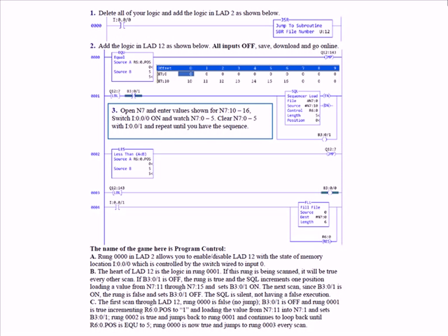In other words, this will not continue to create loopbacks once it's gone through 5 increments until you execute rung 4. When you turn on input 1, that clears R60, and it also clears N70, and you can start over again. So this is just a little demonstration of how you would jump backwards. Why you would jump backwards: if you want to execute, in this case, rung 1 5 times and then go on with the program.